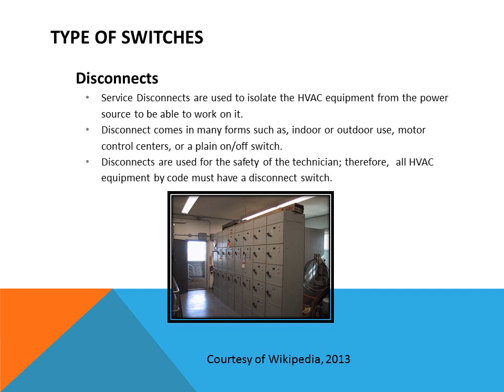Service disconnects are used to isolate the HVAC equipment from the power source to be able to work on it. Disconnects come in many forms, such as indoor or outdoor use, motor control centers, or just a plain on and off switch. Disconnects are used for the safety of the technician. Therefore, all HVAC and refrigeration equipment by code must have a service disconnect switch.